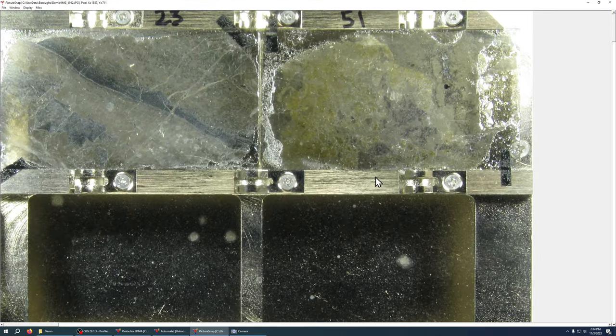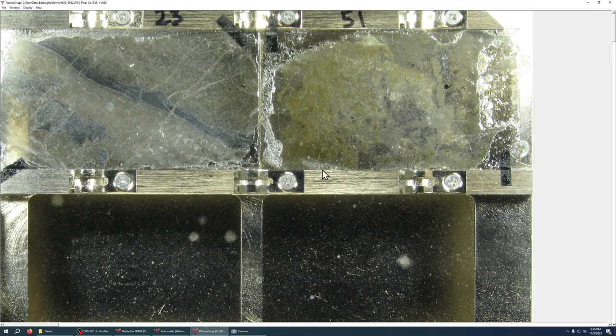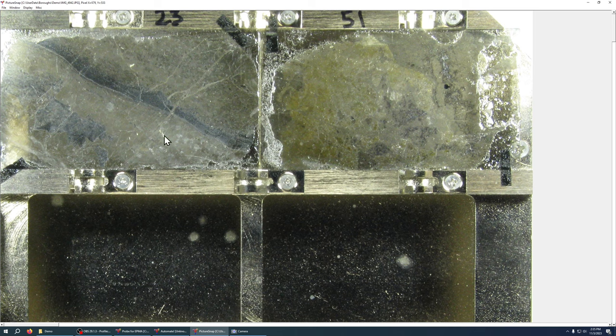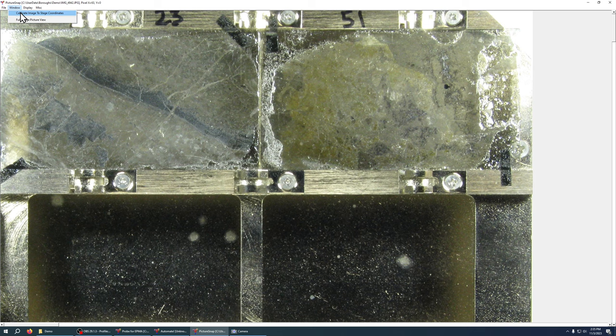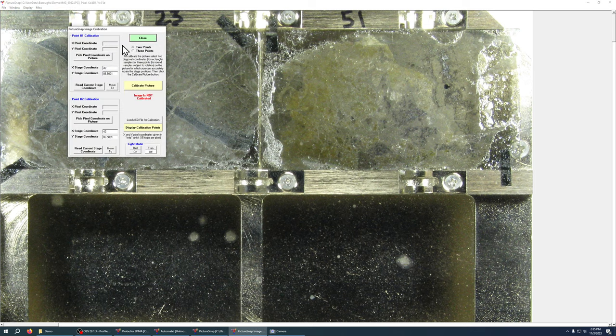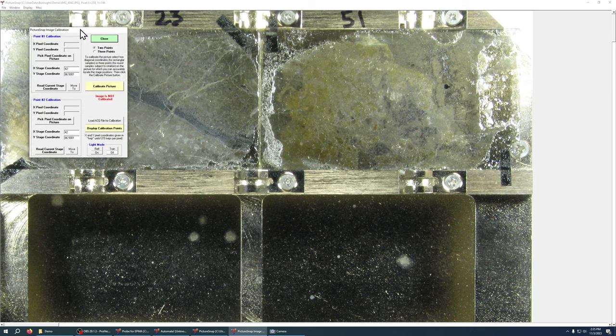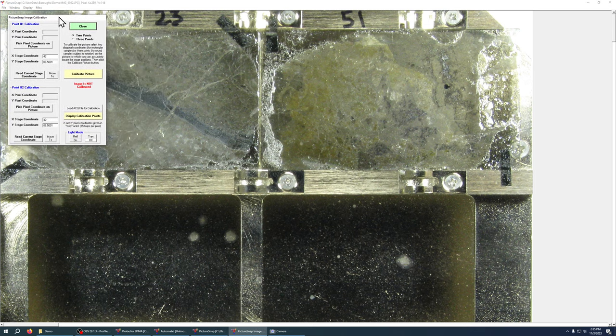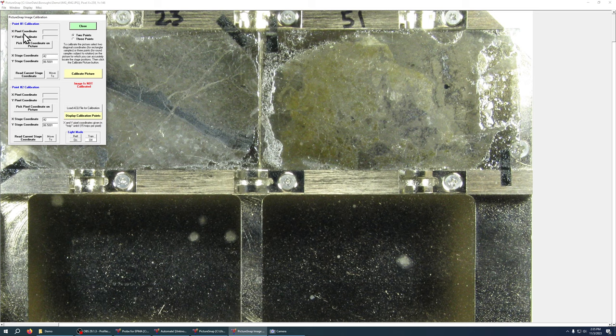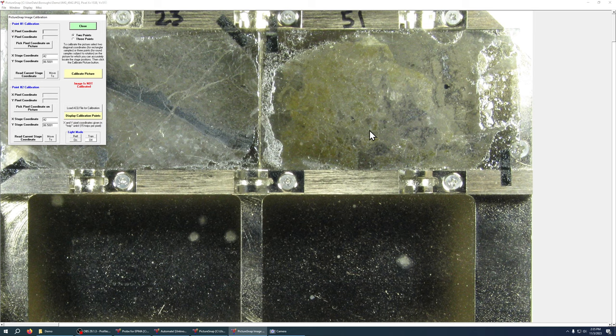So once our image is open we need to calibrate it so PFE knows where pixels on the image are for stage coordinates on the probe. So we're going to go to window, calibrate image to stage coordinates and that brings up this dialog. And here you can see we have Point 1 calibration, Point 2 calibration. So what we're going to do is pick two points on our sample holder that we can see on the image as well as in the actual microscope.